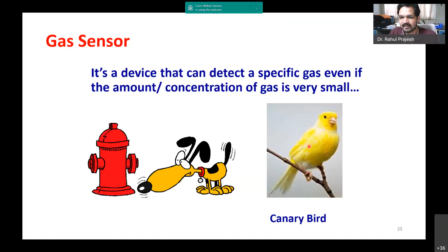So what are the different technologies for gas sensors? First there was the canary bird, then lanterns were used, and then, as science advanced, different technologies became available: resistive gas sensors, capacitive gas sensors, acoustic gas sensors, and optical gas sensors. In resistive gas sensors, we use the change in resistance to measure the gas concentration. In capacitive gas sensors, we use the change in dielectric constant and relate that change to the gas concentration. Then there is the acoustic gas sensor, where the resonant frequency of the particular system or sensor is used to measure the gas concentration. And in optical gas sensors, we use absorption, reflectance, or refractive index parameters to judge the concentration of gas.